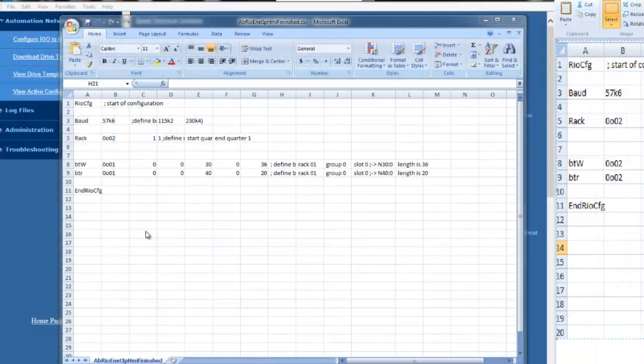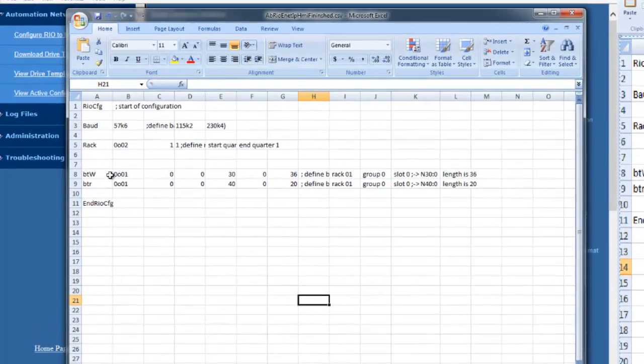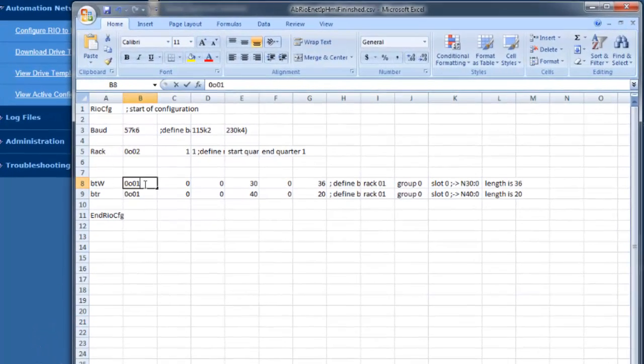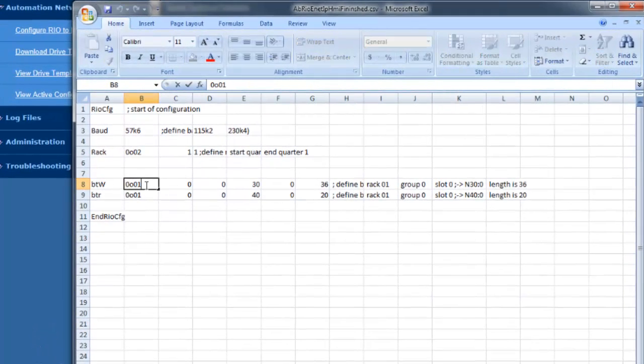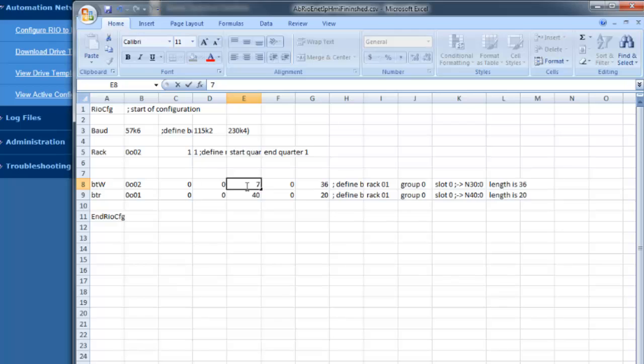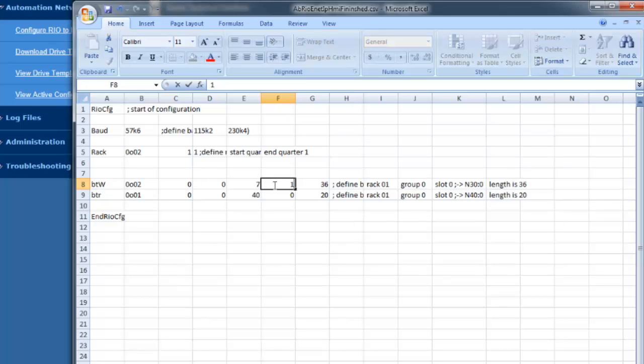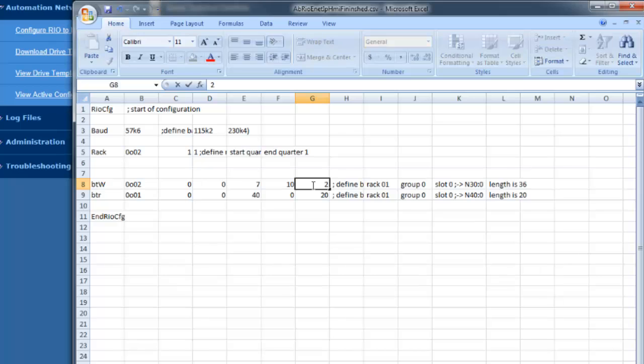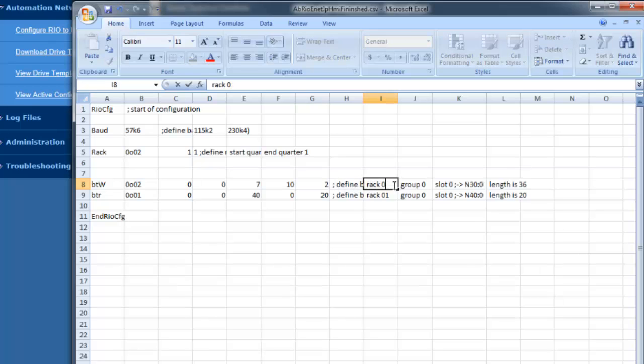Knowing the BTR and BTW information, we can now finish configuring the CSV file. We'll configure the BTW. Start by changing the rack to 2. Group and slot can stay at 0. The file number that the block transfer write was using in logic was N7. The CSV doesn't need the file letter, just the number. It's using the tenth word in the N7 file, so we'll enter 10, and the length of the BTW was two words.